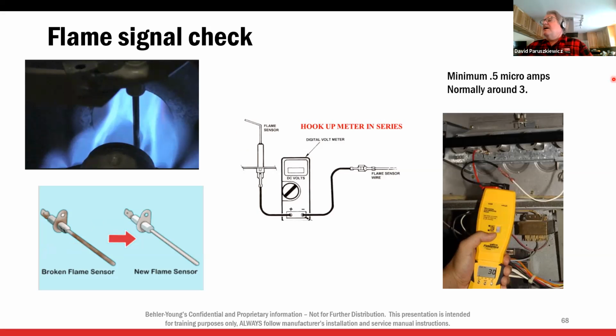Now, a flame signal. A microamp is a millionth of an amp. All right. Now, amperage measures current flow, right? So what happens is we send an electrical current down this flame rod. The flame picks it up and carries it to ground. It's very high resistance, but a flame is a conductor. So we've got a very high resistance short. And it's in microamps, millionths of an amp.